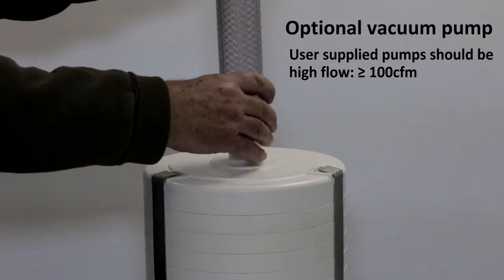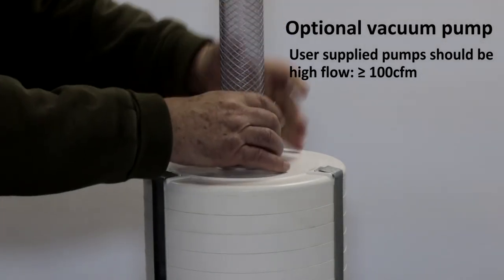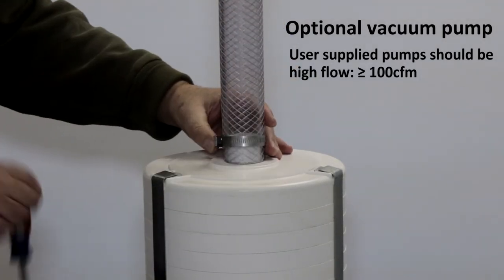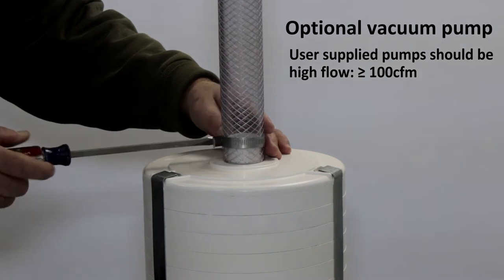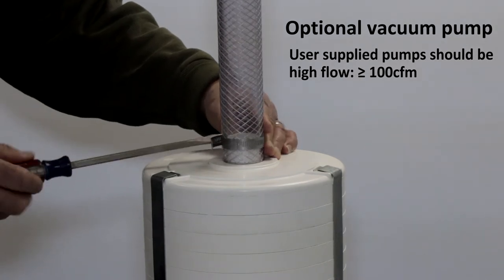Take the 2-inch tube with hose clamp and place on the top inlet of the pump. The hose clamp should be snug, but do not over-tighten as that may crack the inlet of the housing.